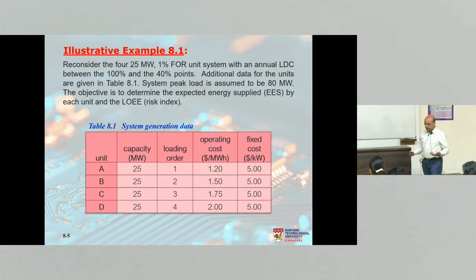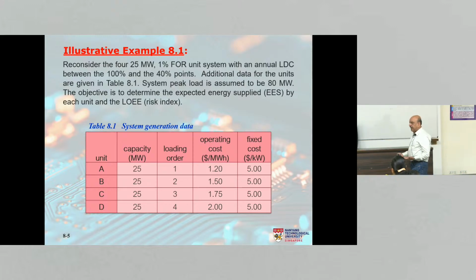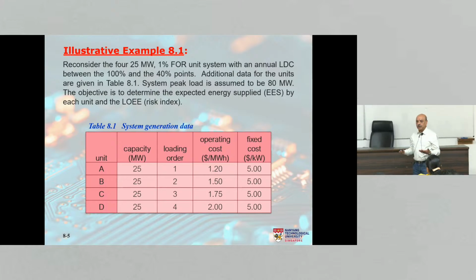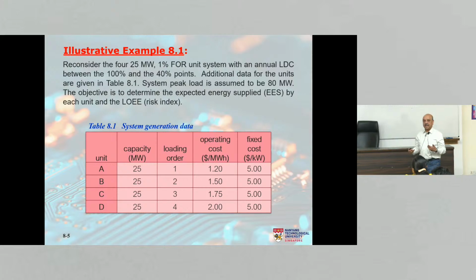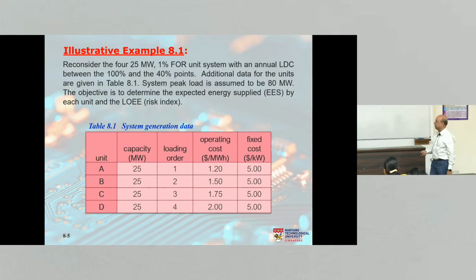The good thing about this method is that you not only calculate the risk, you also calculate how much energy each generator is supplying. That is a byproduct of the method. So in a way, you are getting more information as opposed to the loss of load expectation method. So let's look at this system data, 25 megawatt, 1% FOR. You know how to calculate the COPT, correct?